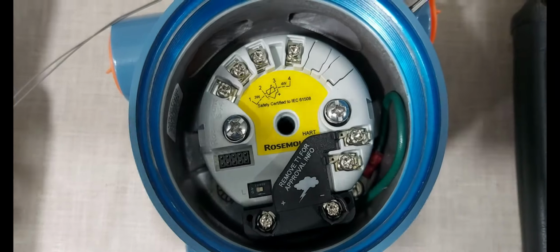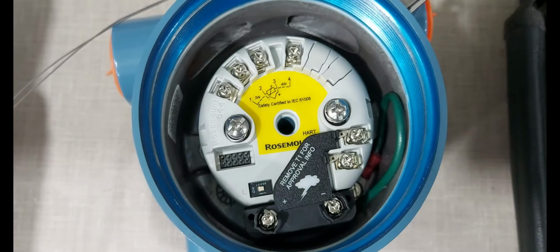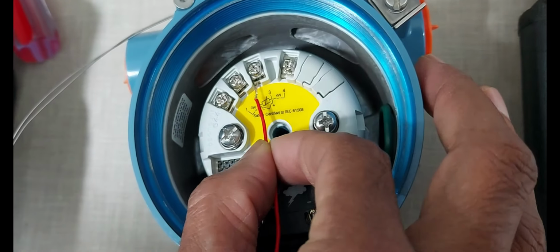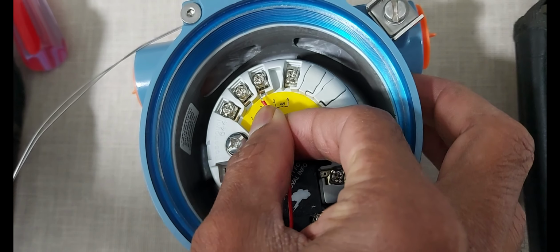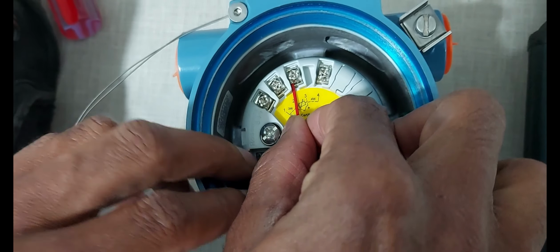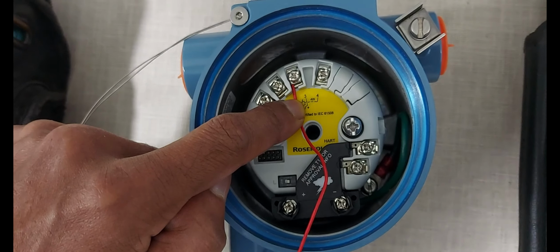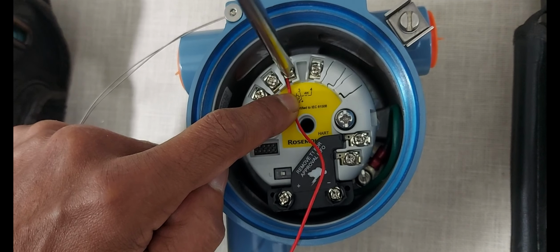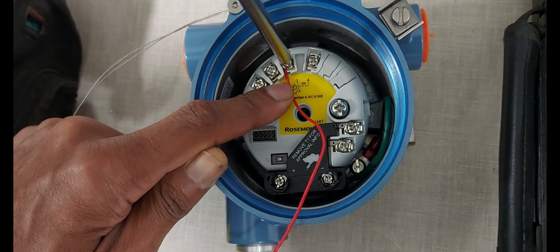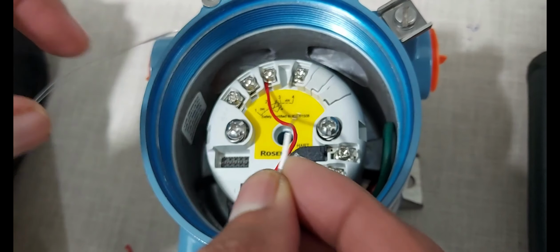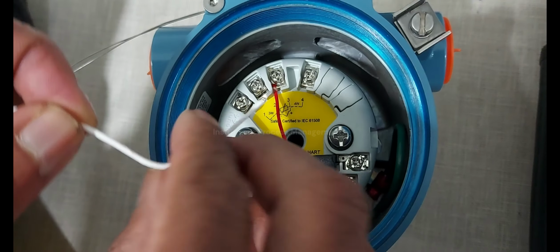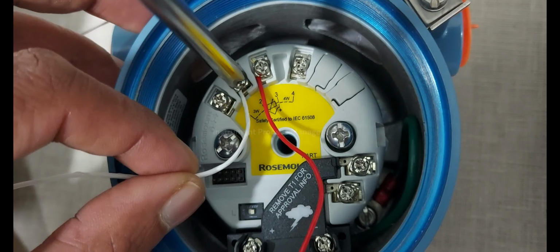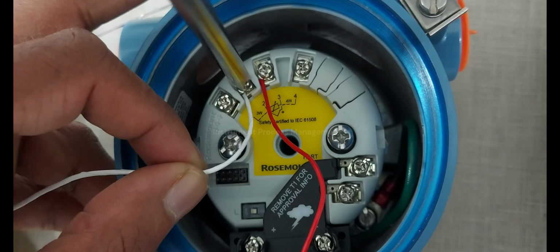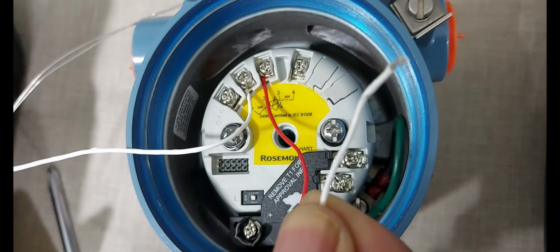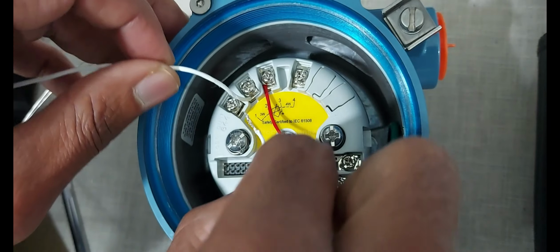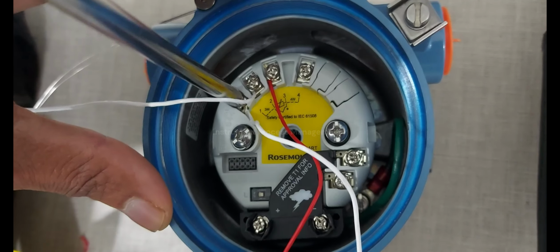Next connect the RTD cable to terminal numbers 1, 2, 3. First I am connecting the red cable to terminal number 3. Right. Okay. Next I am connecting the white cable to terminal number 2. Tighten the cable. Next the other white cable is connected to terminal number 1. Tighten the cable.